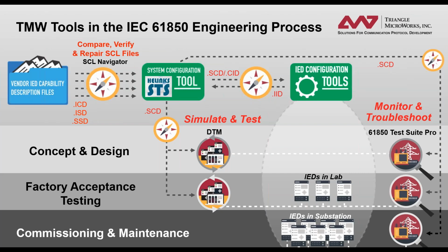Yes. However, there are several config revisions throughout the file, whose control blocks carry one to indicate if data sets have changed, but at the IED level, yes. Yeah, the configuration revision relates, as an example, to control blocks, when the tool is modifying them it typically increases the revision of the configuration.